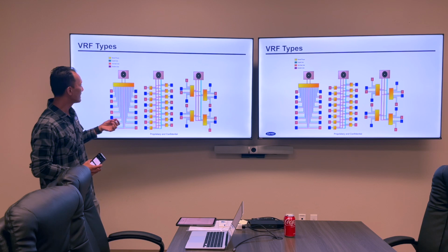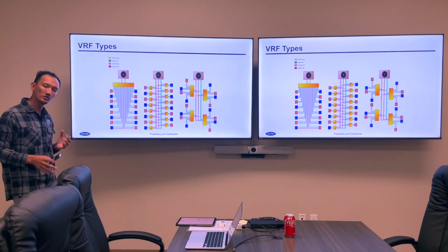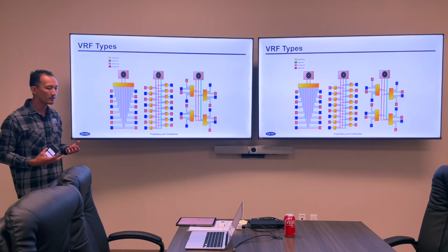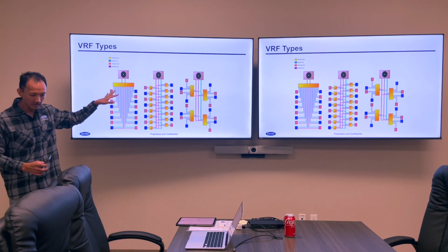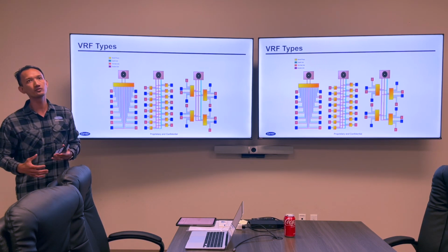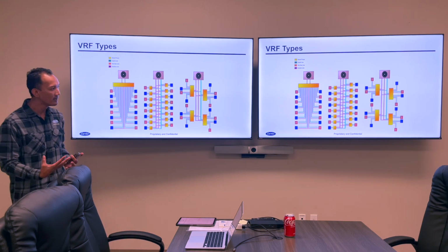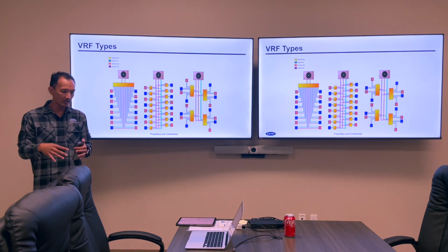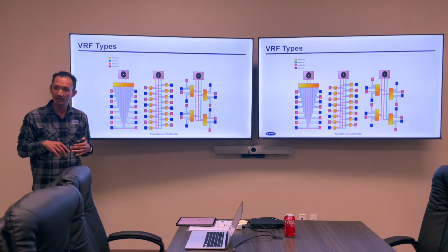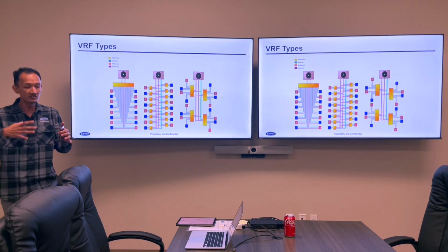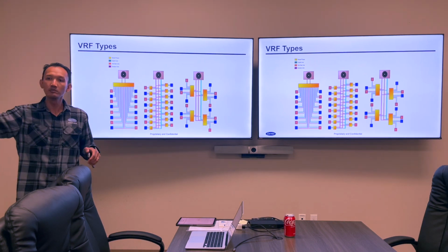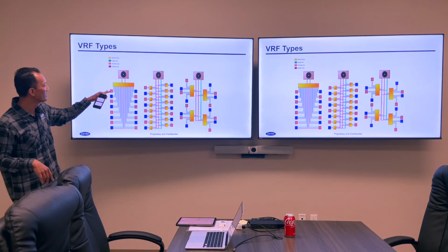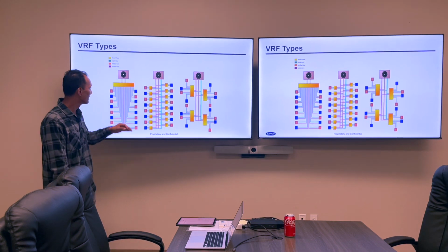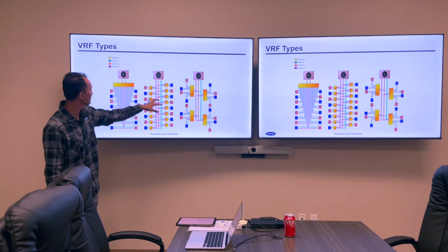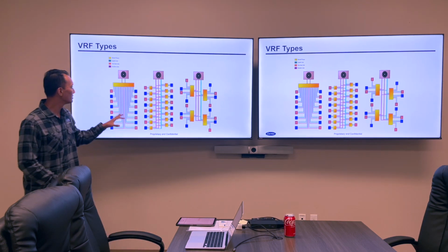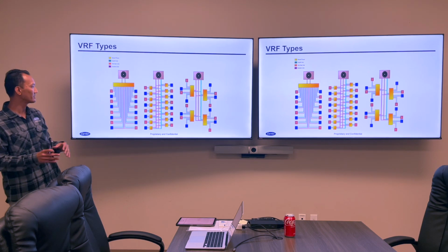One of the things that we get asked all the time is, where would we use two-pipe, where would we use three-pipe? What type of application would dictate one design versus the other? Generally speaking, a two-pipe system, we like to use those for maybe low to mid-rise office buildings, or any building where you've got maybe a large central location. It's not rectangular, it's more or less square, where you can place one of these boxes centrally, and then say if there are offices around the perimeter of the building, you can then pipe from your box all the way to the different fan coils. These things are a little bit large compared to the three-pipe, the flow selector box compared to the three-pipe. So generally you want to place these centrally and then branch out.